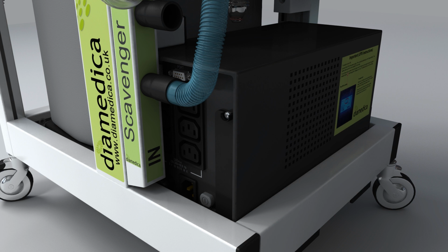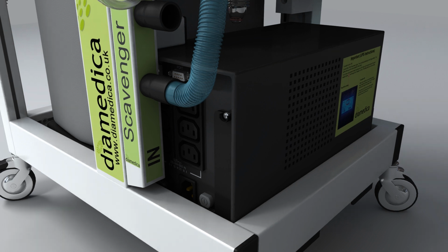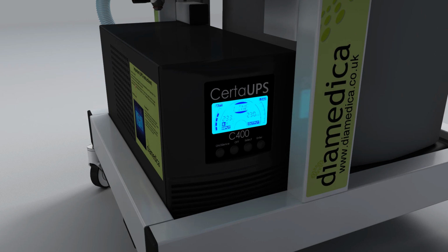To enable battery backup and voltage stabilization, hold down the ON button. The display will move from bypass to line mode. To turn the UPS off after use, hold down the OFF button and the UPS will move from line to bypass mode. When disconnected from the power supply, after a few moments the UPS will automatically shut down. If the power is disconnected while the UPS is in line mode, the device will assume there has been a power failure and the battery will be depleted over time. External patient monitoring can also be connected to the UPS.